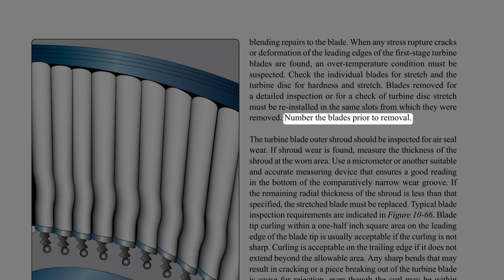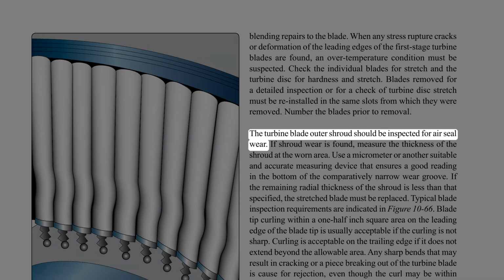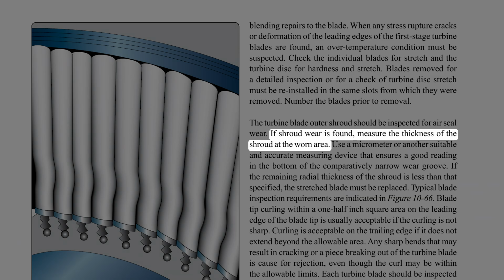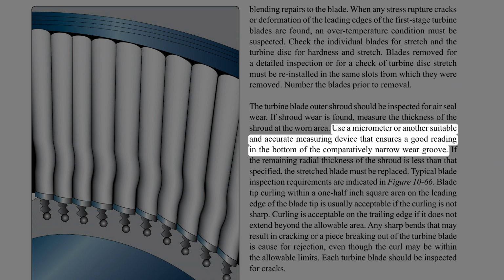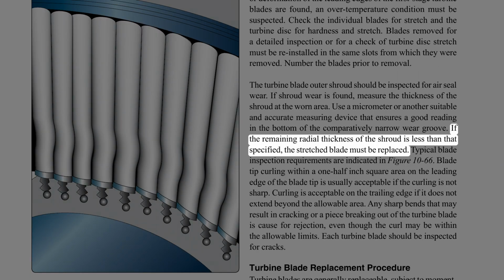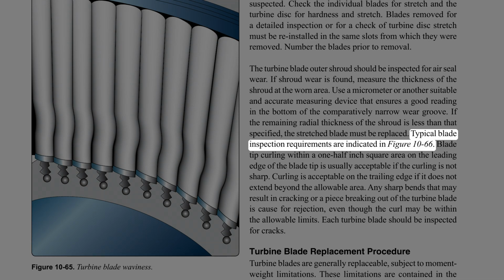Number the blades prior to removal. The turbine blade outer shroud should be inspected for air seal wear. If shroud wear is found, measure the thickness of the shroud at the worn area. Use a micrometer or another suitable and accurate measuring device that ensures a good reading in the bottom of the comparatively narrow wear groove. If the remaining radial thickness of the shroud is less than that specified, the stretched blade must be replaced. Typical blade inspection requirements are indicated in Figure 10-66.